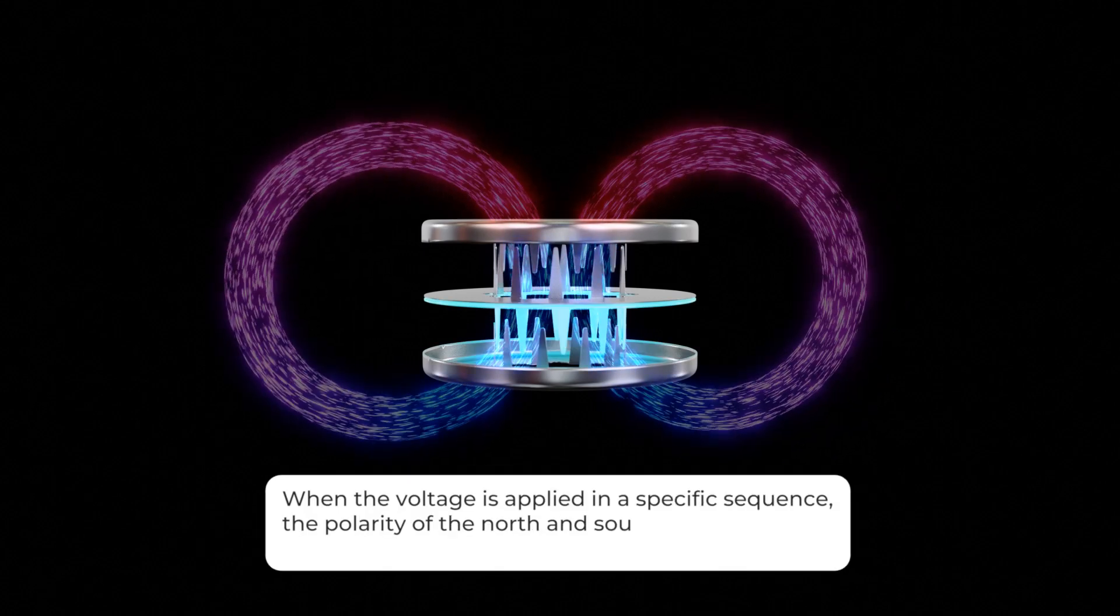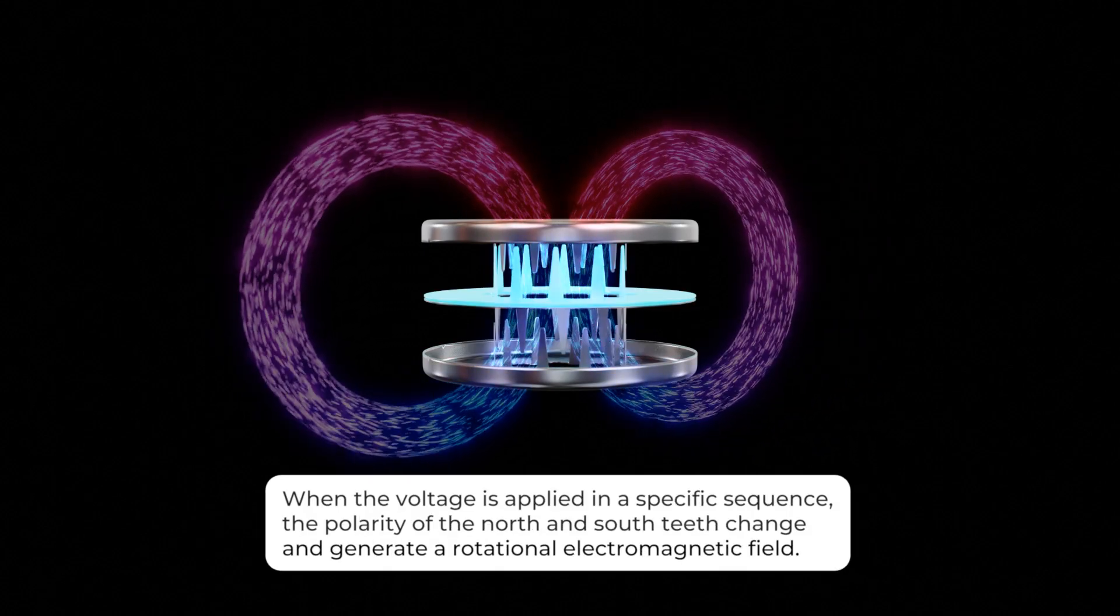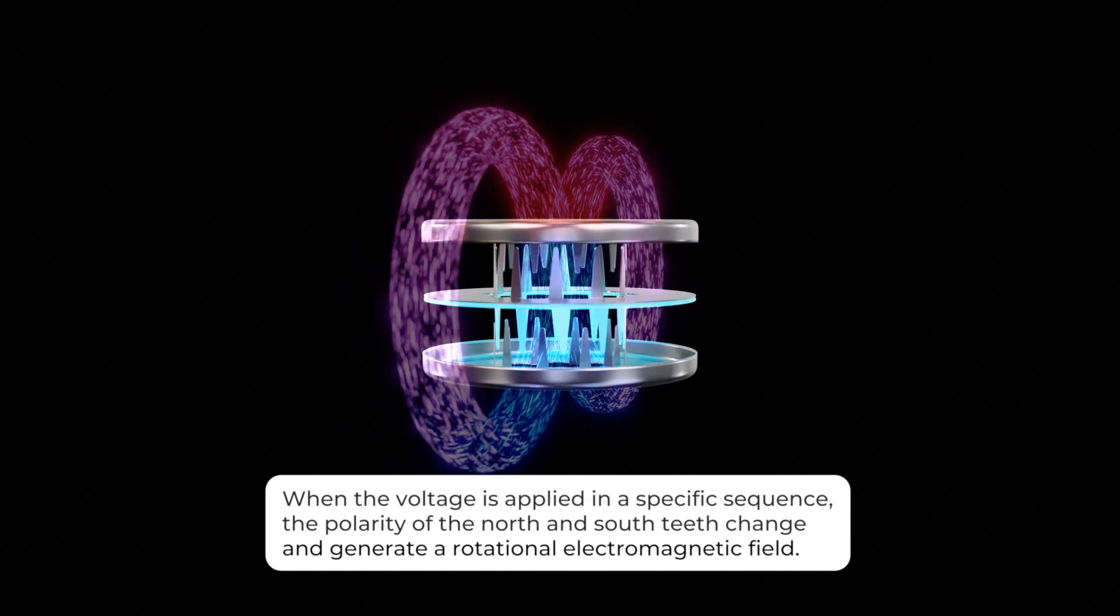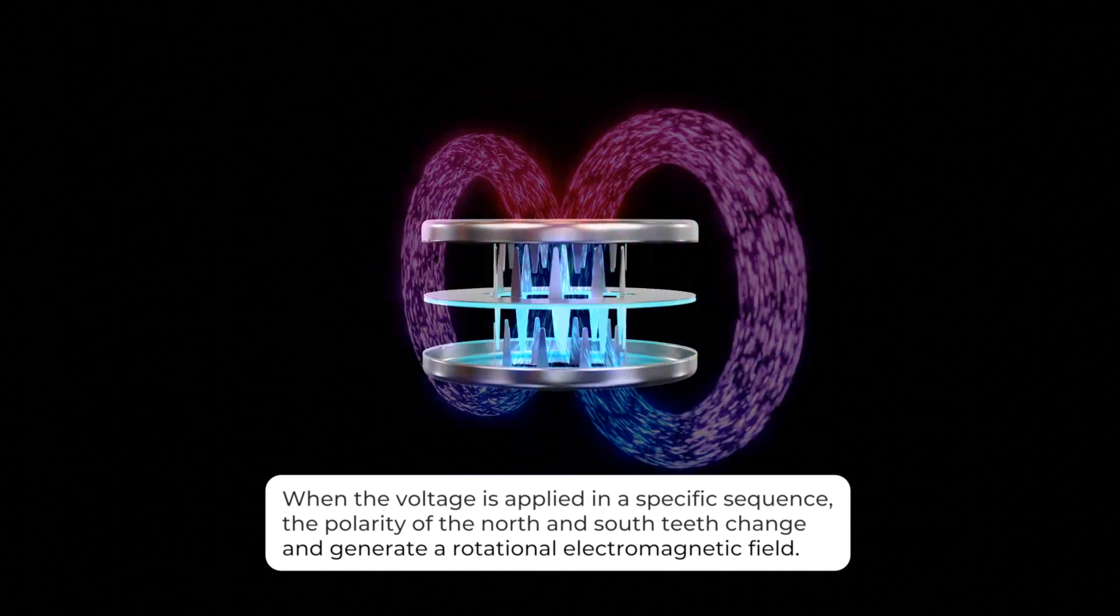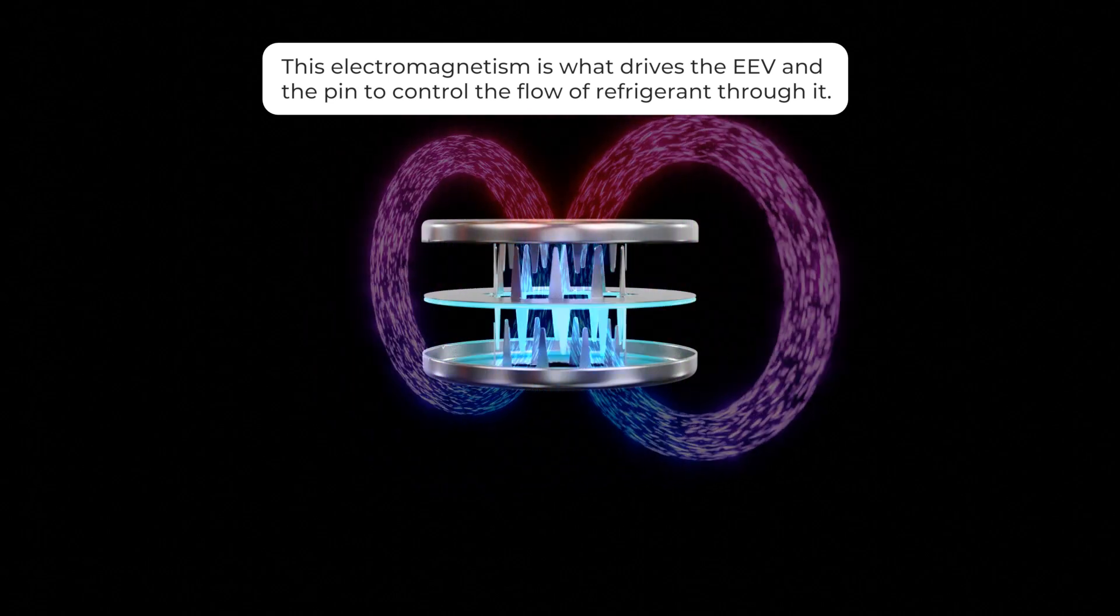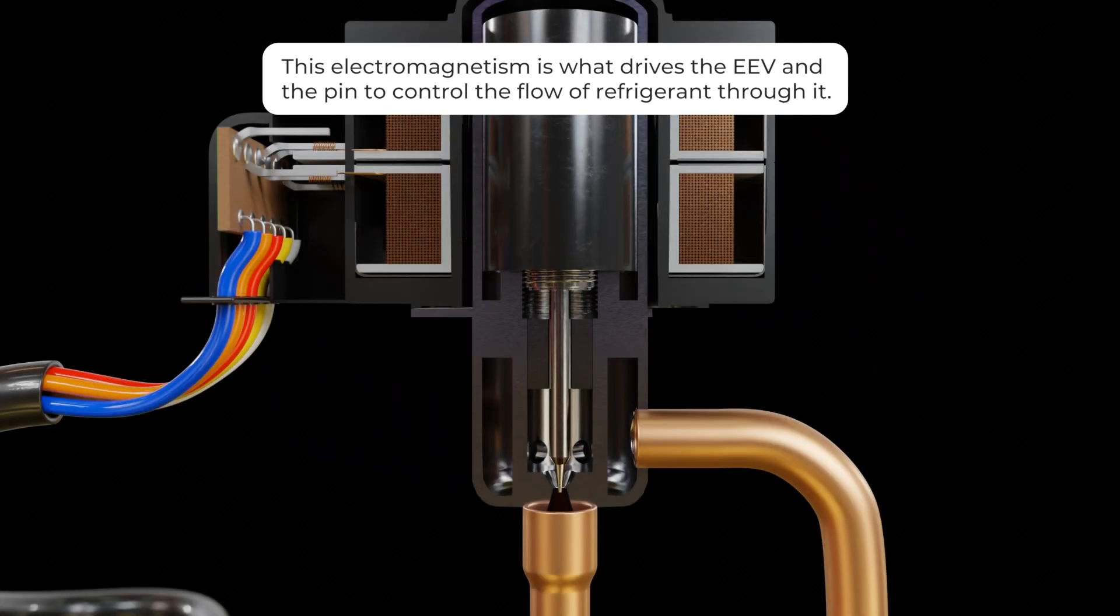Pulses from the board tell the EEV how much it needs to turn to raise or lower the pin. These pulses energize the windings in the coils which magnetize the iron teeth and assign a north and south polarity. When the voltage is applied in a specific sequence, the polarity of the north and south teeth change and generate a rotational electromagnetic field. This electromagnetism is what drives the EEV and the pin to control the flow of refrigerant through it.